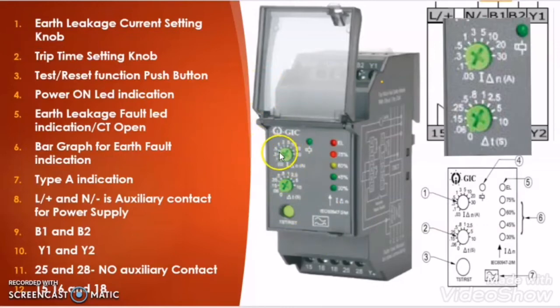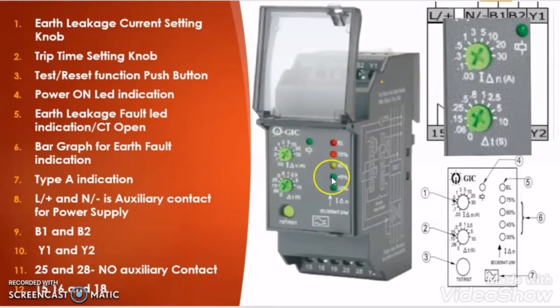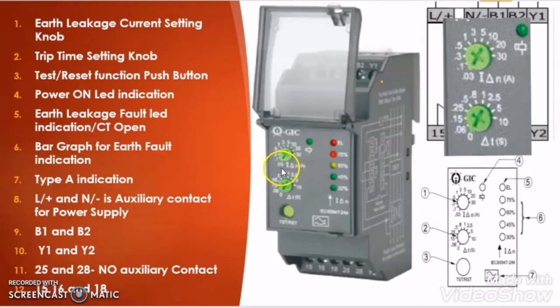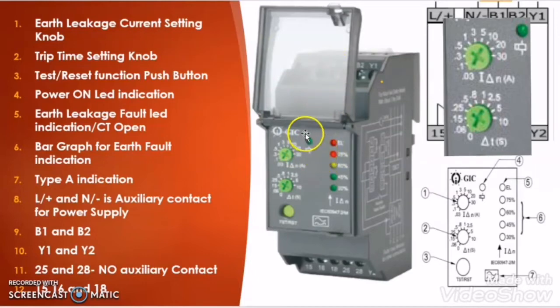To better understand the earth leakage relay, let us understand its important parts. The first thing which you will find on the earth leakage relay is an earth leakage current setting knob. With the help of this knob you can adjust the current rating of the earth leakage relay. You can set the earth leakage relay from 30 mA to 30 Ampere. Suppose you set the knob at 10 Ampere — whenever the earth leakage relay senses earth leakage current with the help of CBCT more than 10 Ampere, it will give command to the circuit breaker or contactor to trip.